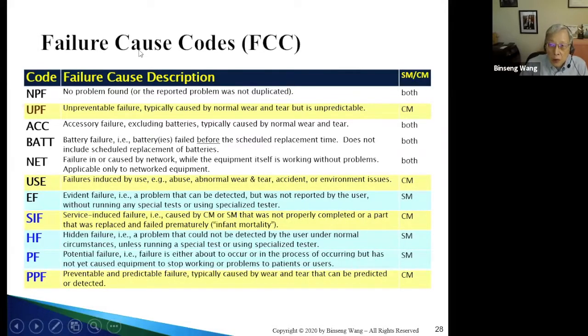So what are the causes that we want to understand? We will use a very small number of causes, as small as possible, because we don't want to create a lot of cause codes that make the analysis difficult. And again, you very often don't have enough pieces of equipment to perform analysis. Typically, a hospital has maybe 10,000 or 20,000 pieces of equipment, but when you narrow down to individual brands, models and classes of equipment, very often you find yourself with 15, 20, maybe 100, maybe 200 pieces of equipment at most. So if you dilute that across many, many causes, you will not be able to achieve a reasonable analysis, at least at first hand.